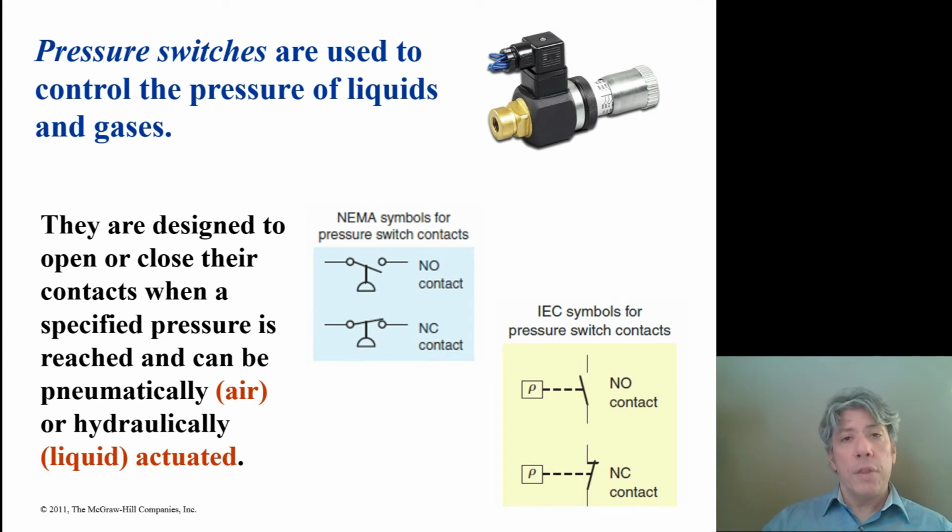So you really want these switches to be operational in the refrigerant system, so that the system only operates when the pressure range is appropriate. But you can get pressure switches for gases, for liquids, for all sorts of things, and they're sensitive to pressure. Some are made to work with gases, some are made to work with liquids, and they're not made to work with the opposite. In fact, they can be damaged with the opposite. So there's a wide range of these switches.